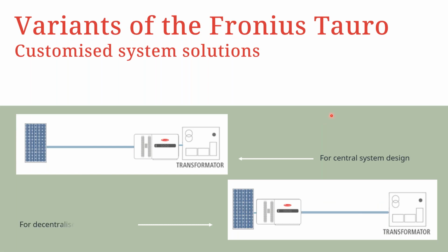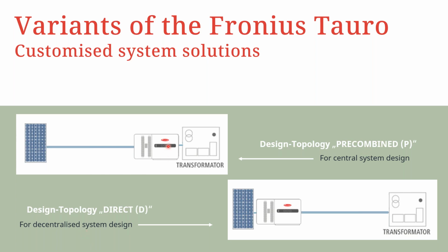So just like we mentioned for the snap inverters, the differentiation between whether it's a central design or a decentralized design. For a central design, we are talking about the Tauro series, the P version, and for the decentralized design, we are talking about the D version. With the D version, like we said, you connect the DC power from the arrays directly to the inverter.